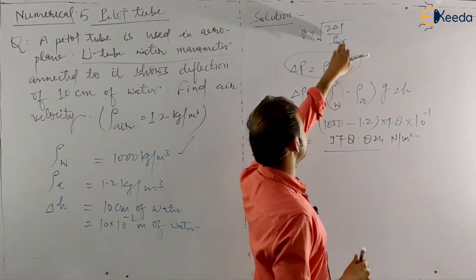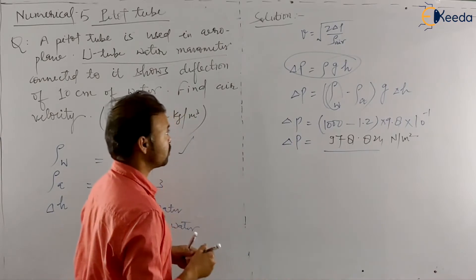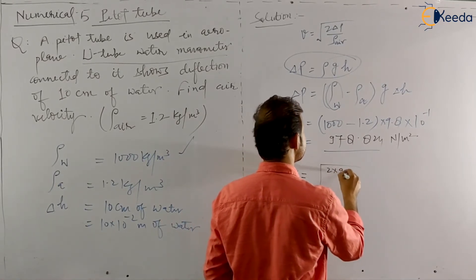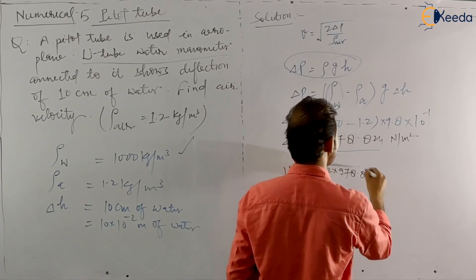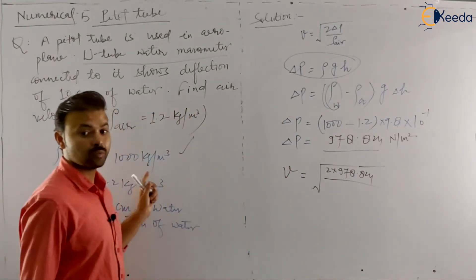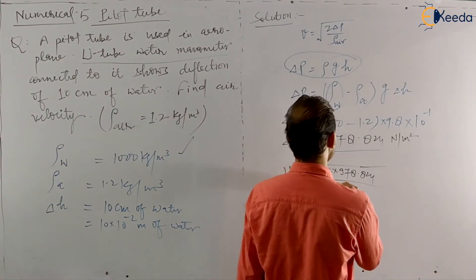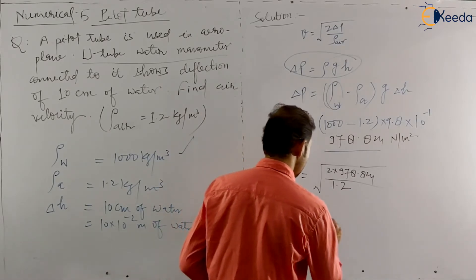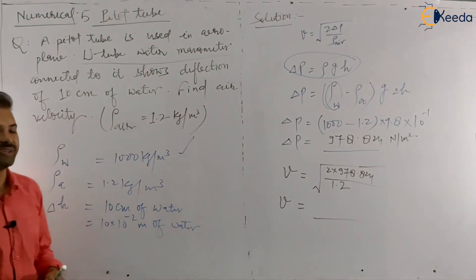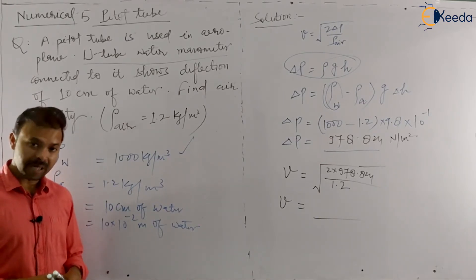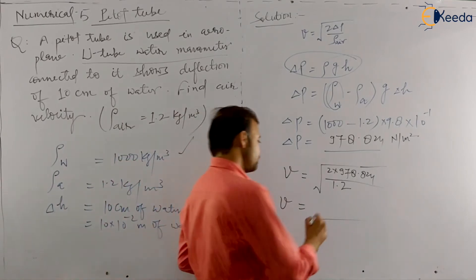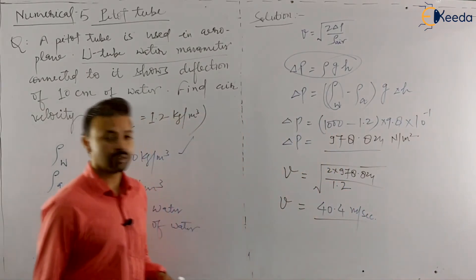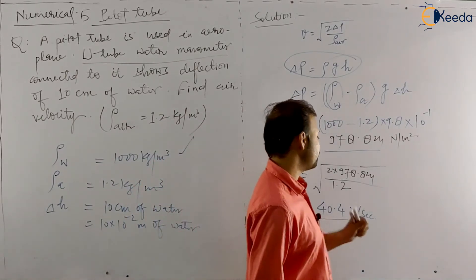Now you have delta P and rho_air, so the velocity of air can be calculated from the pitot tube formula: V = √(2ΔP / ρ_air) = √(2 × 978.824 / 1.2). All units are in the MKS system. Calculate V using your calculator. V should come out as 40.4 meters per second. Verify it — the answer should be 40.4 m/s.